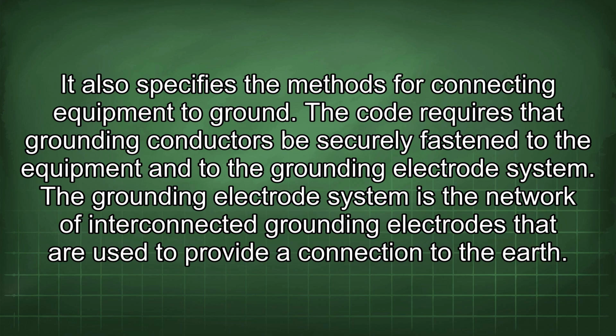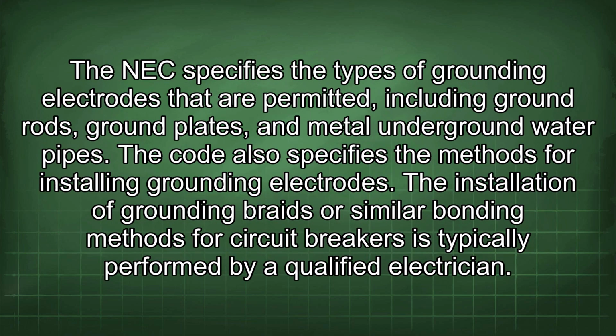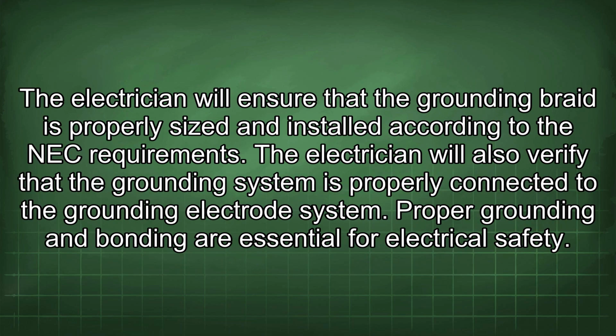The grounding electrode system is the network of interconnected grounding electrodes that are used to provide a connection to the earth. The NEC specifies the types of grounding electrodes that are permitted, including ground rods, ground plates, and metal underground water pipes. The code also specifies the methods for installing grounding electrodes. The installation of grounding braids or similar bonding methods for circuit breakers is typically performed by a qualified electrician. The electrician will ensure that the grounding braid is properly sized and installed according to the NEC requirements. The electrician will also verify that the grounding system is properly connected to the grounding electrode system.